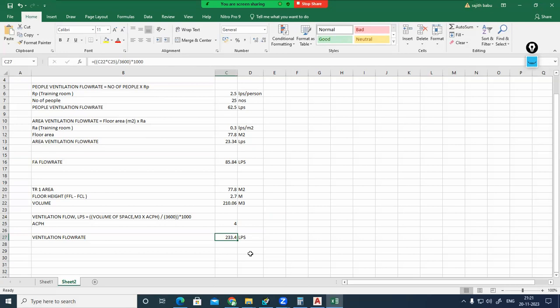But the air changes per hour method, we are not using in the conventional system. We are using it in healthcare facilities. So you should know, normally for comfort air conditioning systems, this kind of hotel building, office building, everywhere, we are using this ASHRAE 62.1 standard only, but it doesn't mean that each and every building it is possible to design using ASHRAE 62.1. For healthcare facilities and all, we might be using a different standard. There, the fresh air demand, we are not calculating with respect to the ASHRAE 62.1 method. We'll be calculating the fresh air demand with respect to the ACH method only. So how much ACH has to be considered?